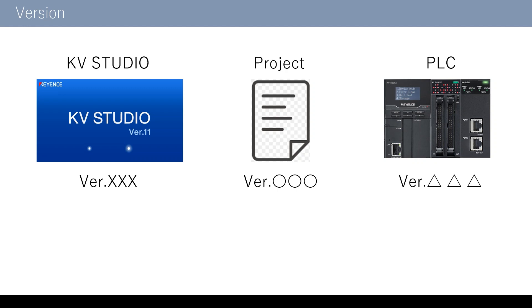What if the project version is newer than the PLC version? In this case, you can update the PLC first, then transfer the project with the new version. Once the project version is updated, new functions of the PLC become available. If you want to use a new function for a project created before, please update the project version first, then update the PLC version. Now you can transfer the project.